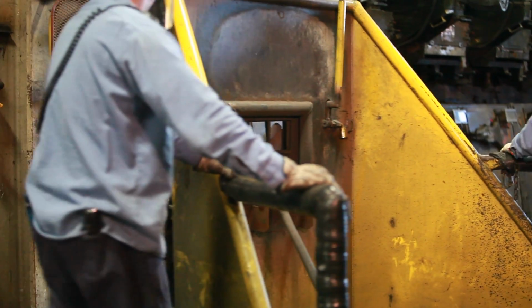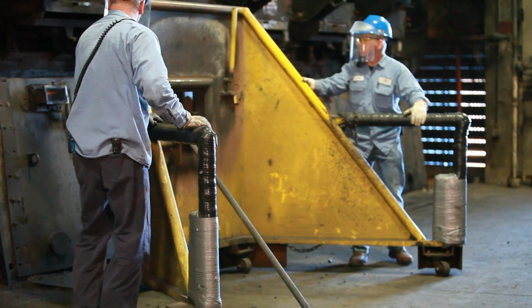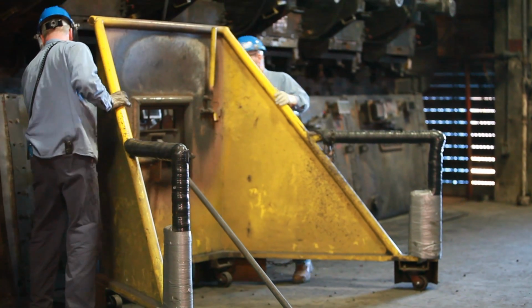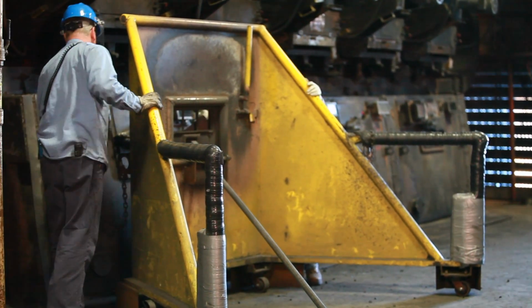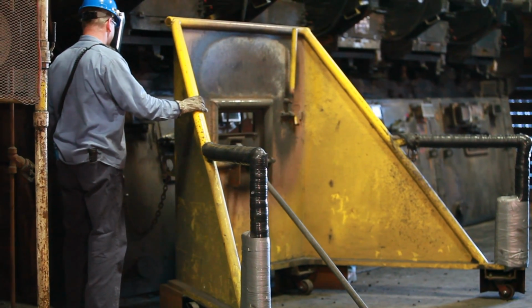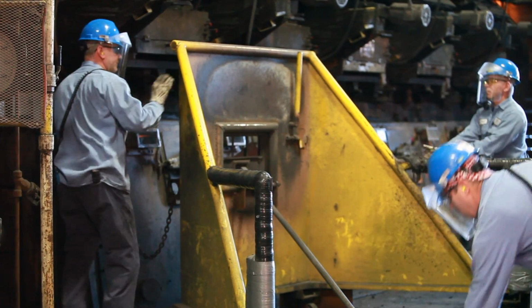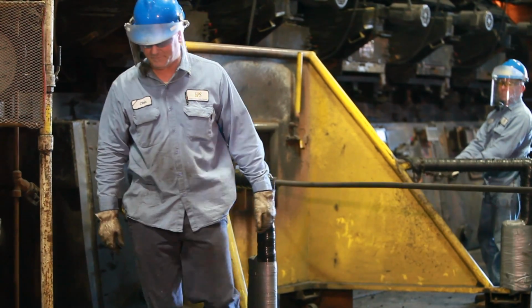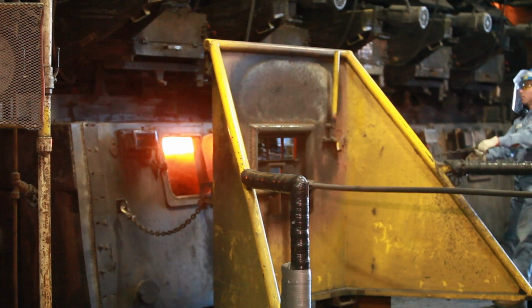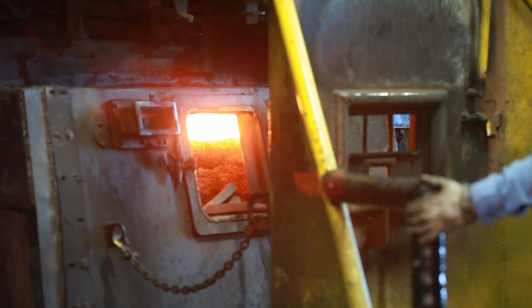Edgecombe engineered better mobile rolling work platforms and rolling heat shields to provide protection to the employees while working on feeders and raking grates. Fire retardant blankets are now draped over the front of the boiler when working on feeders and distributors to minimize heat and hot surfaces. The last resort is PPE, to which in addition to steel-toed boots, hard hats, hearing protection, and safety glasses, the operators wear FR clothing, thermal gloves and sleeves, and face shields.